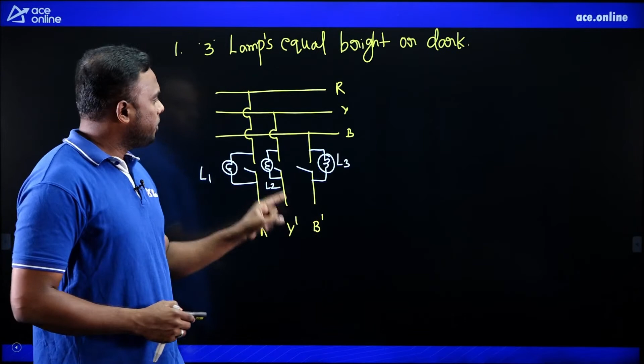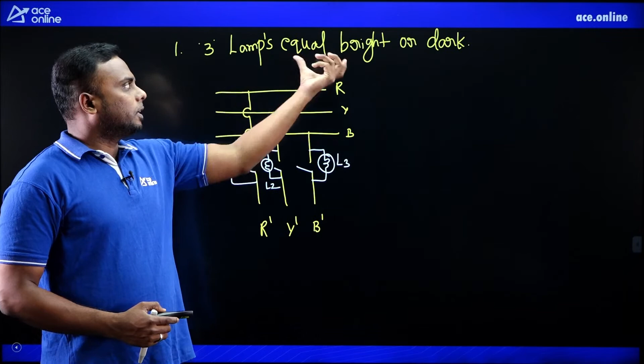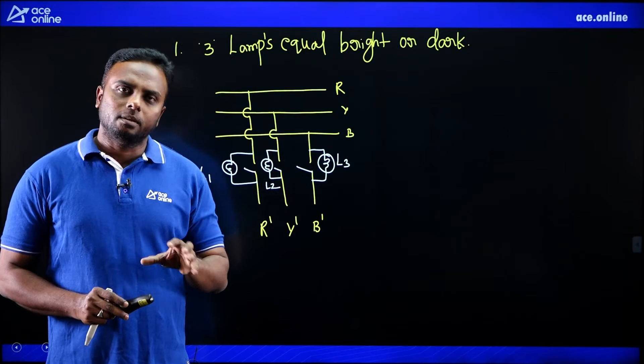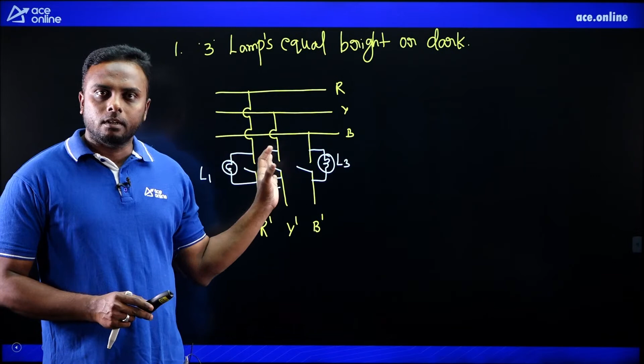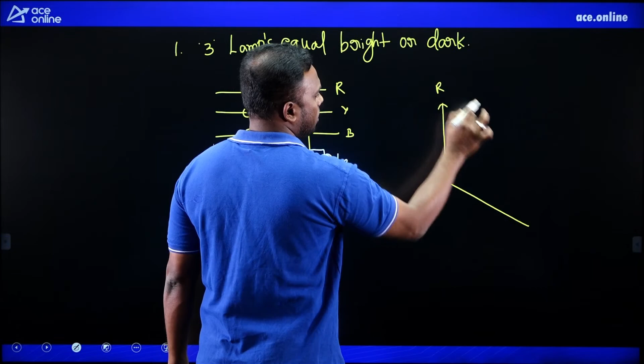So the 3 lamps L1, L2, L3 are connected between RR dash, YY dash, BB dash, and we check for this condition: the 3 lamps should give equal brightness at a time or equal darkness at a time. It is not that one is bright, another is dark, and another is a little more bright. All 3 lamps should show the same brightness at a time, or all 3 the same darkness at a time, either one, because we cannot say which one will come once connected. So when will the lamps show equal brightness? See here, suppose the bus bar 3 phases are R, Y, B.